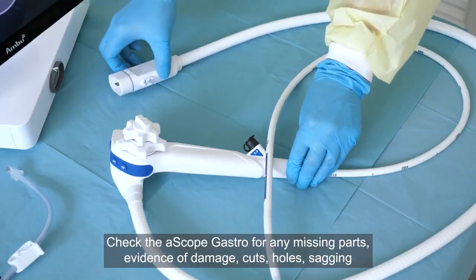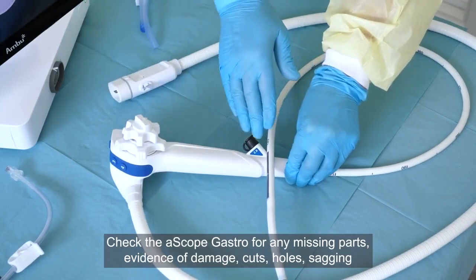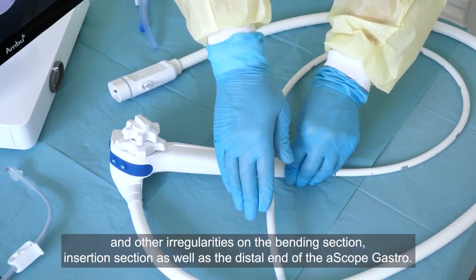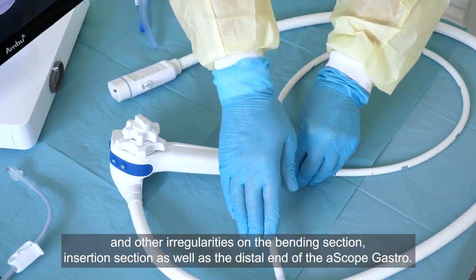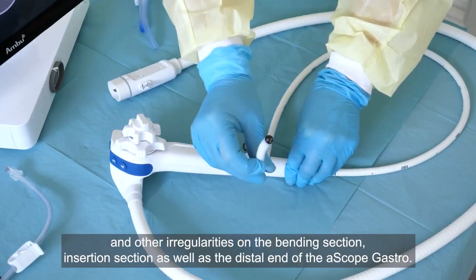Check the aScope Gastro for any missing parts, evidence of damage, cuts, holes, sagging or other irregularities on the bending section, insertion section, as well as the distal end of the aScope Gastro.